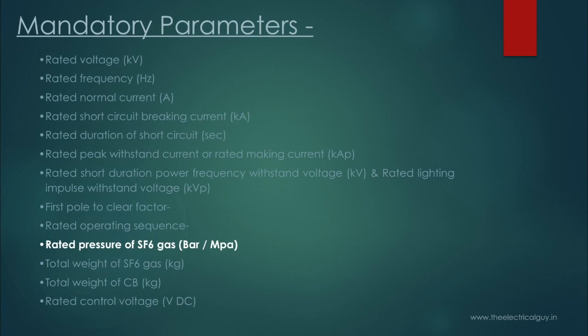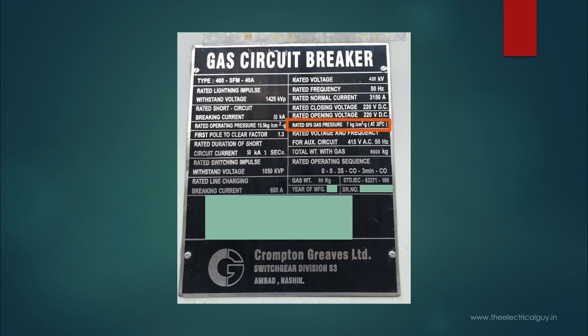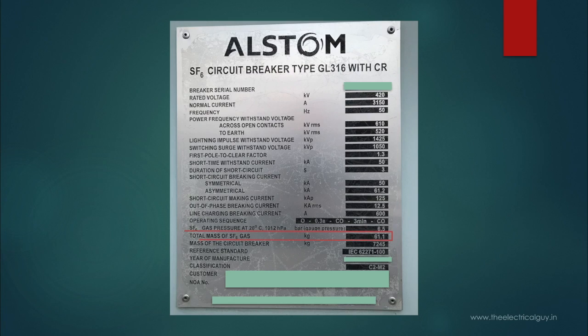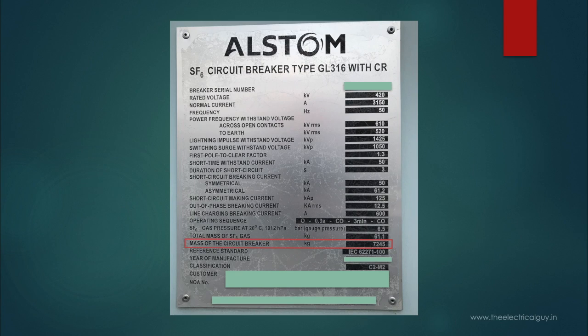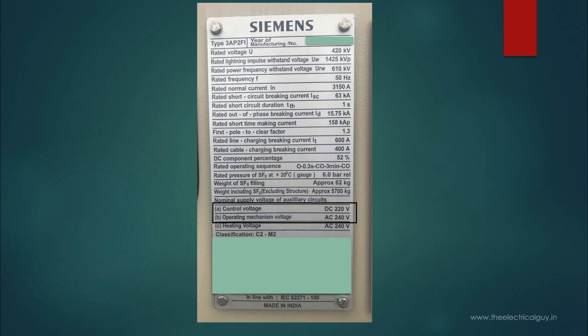Rated pressure of SF6 gas is the rated gas pressure in the breaker, which can be mentioned in bar, megapascals, or kg/cm² and varies manufacturer to manufacturer. Total weight of SF6 gas — this also varies manufacturer to manufacturer. Total weight of the circuit breaker indicates the total mass in kilograms. Rated control voltage is the DC voltage on which the closing and tripping coils work. These were the mandatory parameters as per IEC, which you will generally find on every nameplate of high voltage SF6 circuit breakers.